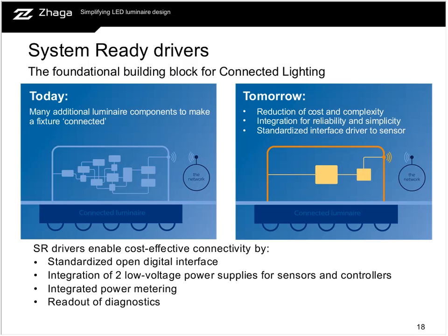One of the reasons that there is a lot of complexity is also that mains functionality is now going to both the driver and the connectivity module, which means that there is a lot of functionality doubled in the system, which also induces extra cost. So what we are targeting in this SR driver concept is to have a standardized open digital interface. There is also an integrated low voltage power supply to power sensors and control functionality. Integrated in the driver is also the power metering function, and there is the option to read out diagnostics.